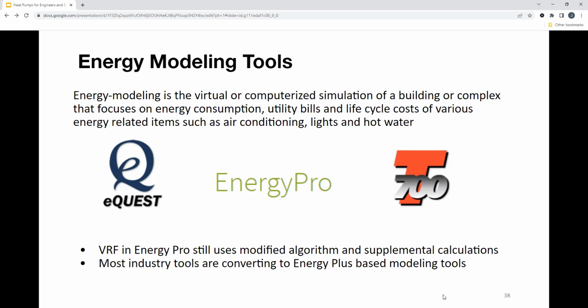One thing I'll mention is that VRF in EnergyPro still uses a modified algorithm and supplemental calculations, which we're trying to avoid. Most industry tools, I don't know if they've already converted or are starting to convert, are moving to EnergyPlus-based modeling tools. The curve regression's major differences lie in ambient corrections for input power; the adjustments are rated full power for ambient conditions. Basically, it takes the energy input ratio correction factor and integrates it, versus just using supplemental calculations. That's getting integrated into all of these software tools to better represent heat pump technology.